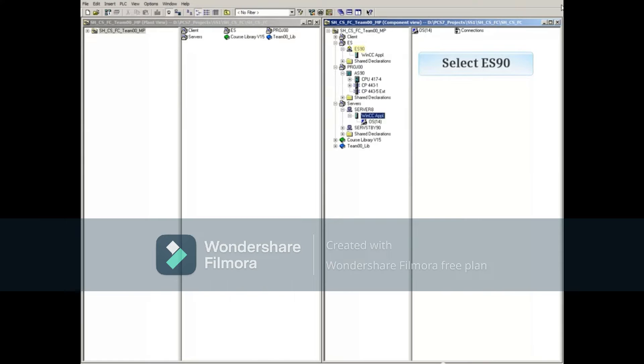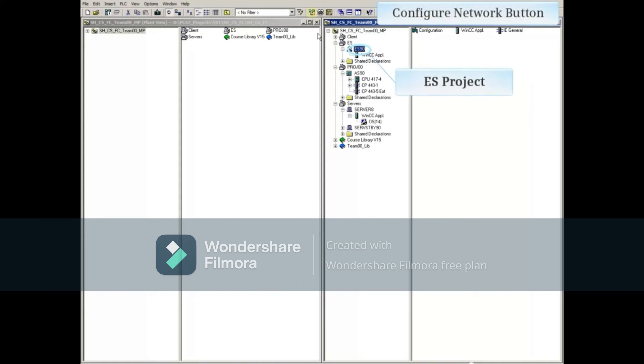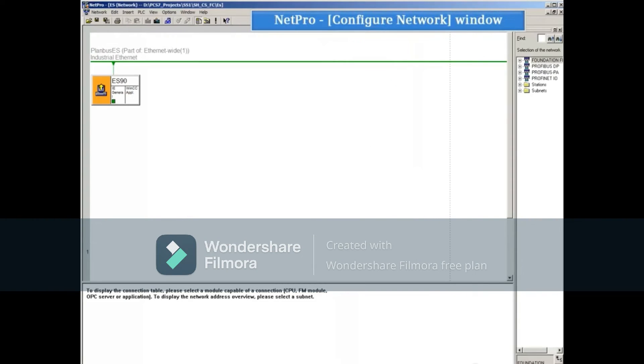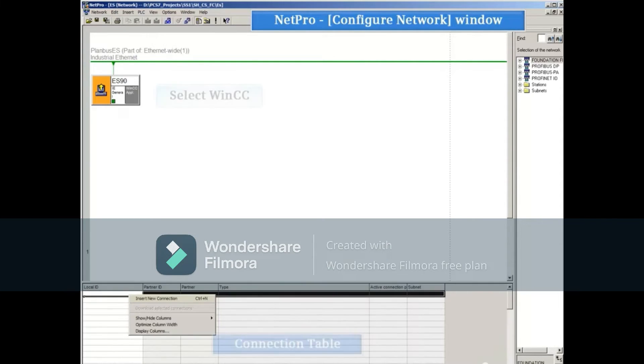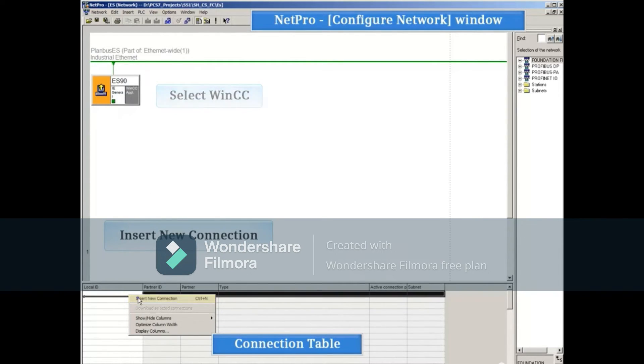If you have an ES station, engineering station, and plan on simulating the OS server with live data, then you need to select an object in the ES project. Open NetPro and make the same connection as you did before for the OS server. Select WinCC and right-click Insert New Connection.